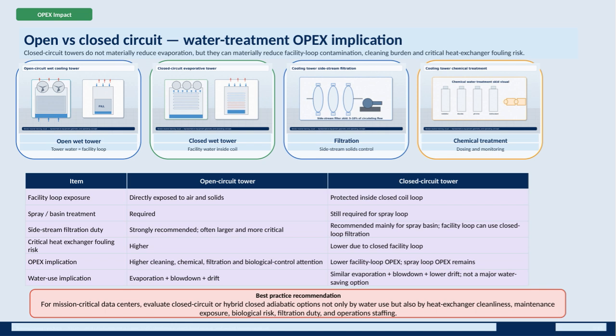In an open wet tower, the tower water is directly part of the facility loop and is exposed to air and solids, which means you need spray and basin treatment, side stream filtration, chemical dosing, and continuous monitoring. These factors lead to higher OPEX due to increased cleaning, chemical use, filtration needs, and biological control efforts.